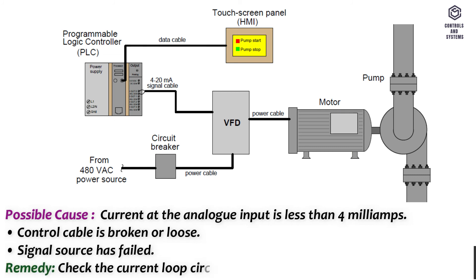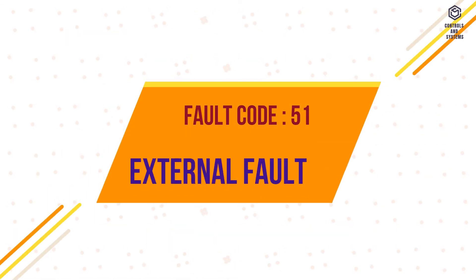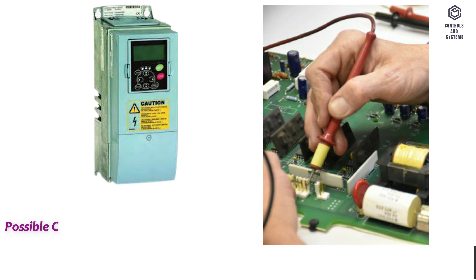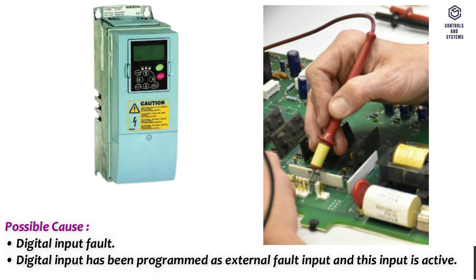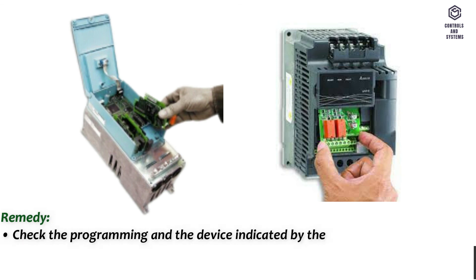Fault code 51 – External fault. Possible cause: a digital input has been programmed as an external fault input and this input is active. Remedy: check the programming and the device indicated by the external fault information, and check the cabling of that device.